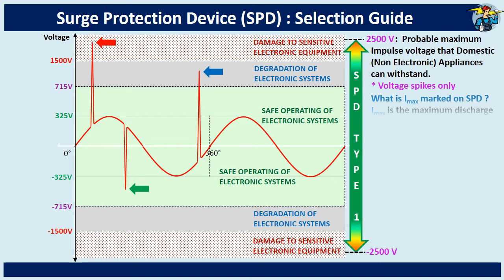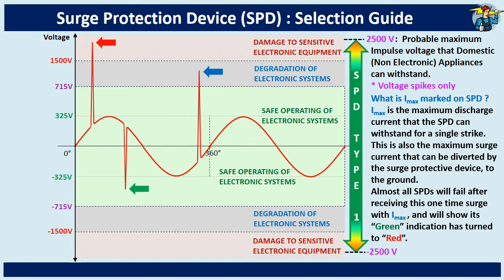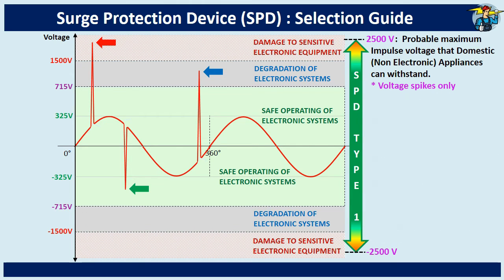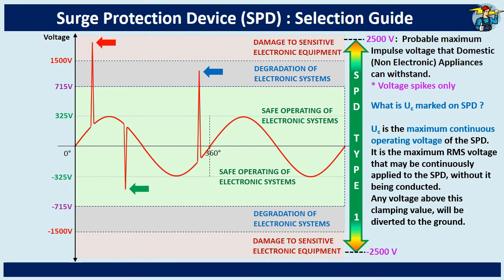What is IMAX marked on an SPD? IMAX is the maximum discharge current that the SPD can withstand for a single strike. This is also the maximum surge current that can be diverted by the surge protective device to the ground. Almost all SPDs will end their lifespan after receiving this one-time surge with IMAX, and will show their green indication has turned to red. What is UC marked on an SPD? UC is the maximum continuous operating voltage of the SPD — the maximum RMS voltage that can be continuously applied to the SPD without it being conducted. Any voltage above this clamping value will be diverted to the ground.